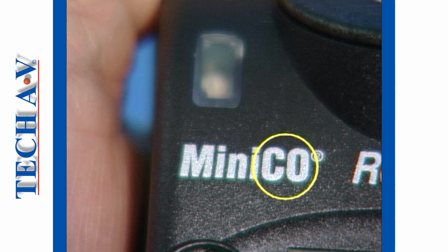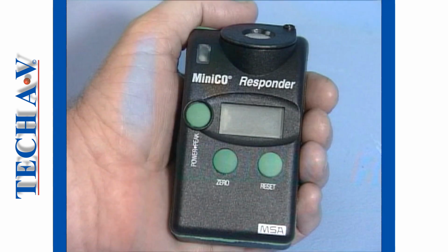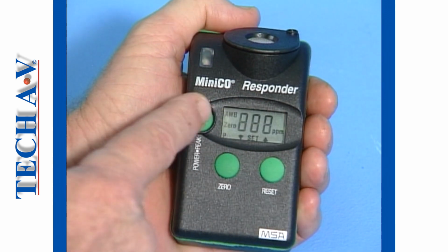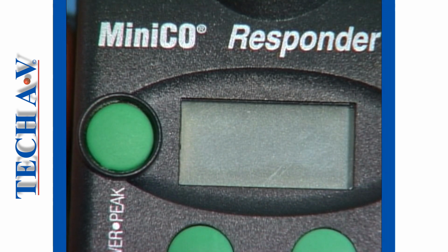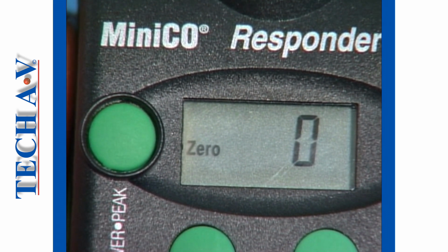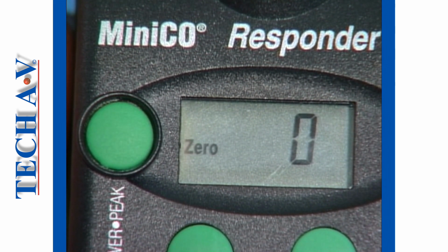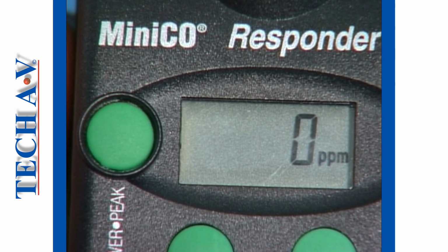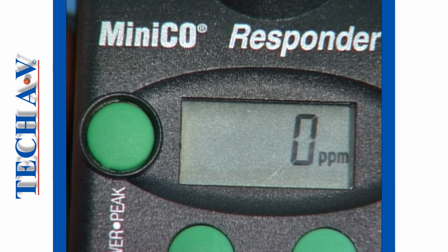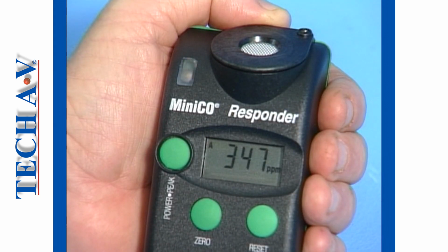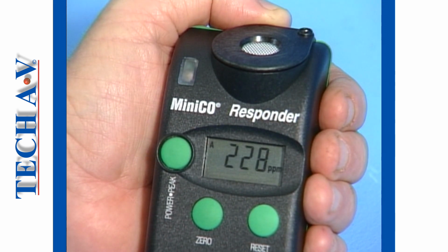Here we have selected a CO, or carbon monoxide, unit. When the instrument is switched on, it first goes through its setup. Once the instrument has performed its internal setup, it will display one item of information, namely the detected concentration of carbon monoxide in parts per million. As with the multiple gas unit, the instrument is calibrated to activate an alarm when the concentration reaches the unsafe proportion for carbon monoxide.